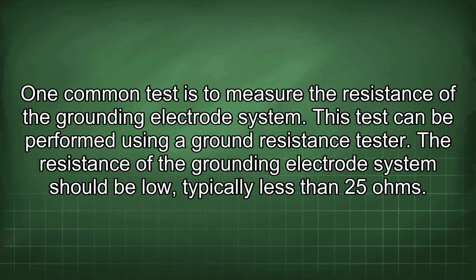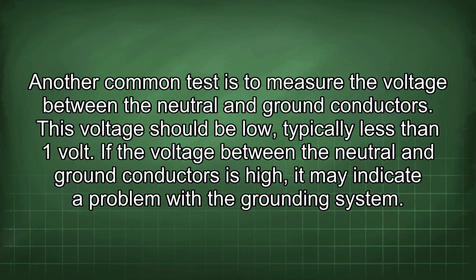One common test is to measure the resistance of the grounding electrode system. This test can be performed using a ground resistance tester. The resistance of the grounding electrode system should be low, typically less than 25 ohms. Another common test is to measure the voltage between the neutral and ground conductors. This voltage should be low, typically less than 1 volt. If the voltage between the neutral and ground conductors is high, it may indicate a problem with the grounding system.